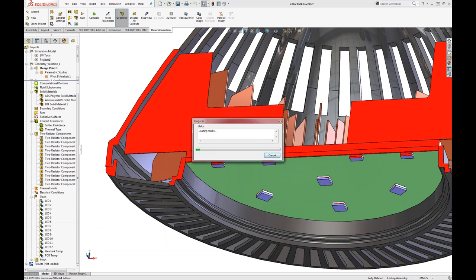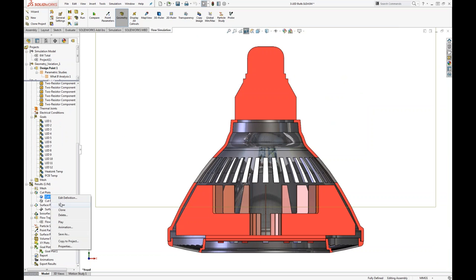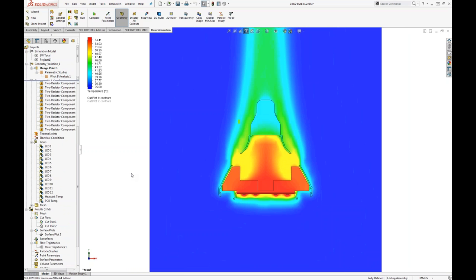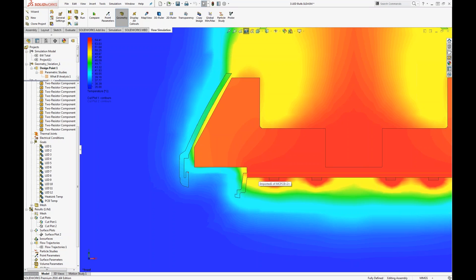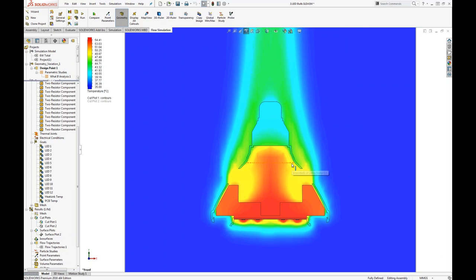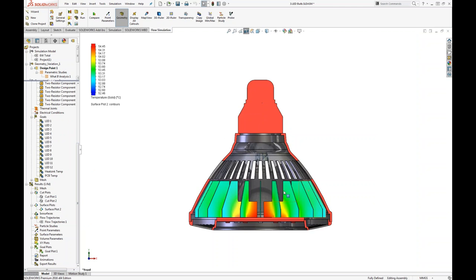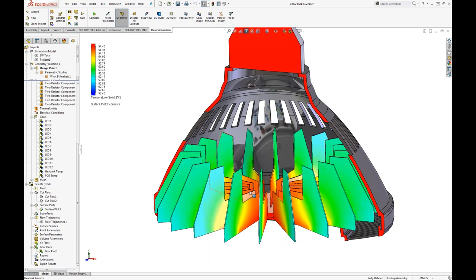Looking at results: a cut plot shows the entire domain including temperature inside both the fluid and the solid materials — in the fins, in the plastics. Gravity is activated, producing natural convection so heated air rises. The surface plot shows temperature directly on the aluminum fin surfaces. The key design question is not trivial: which is the correct number of fins? Too few fins and insufficient heat exchange; too many fins and the air cannot pass through to exchange heat.